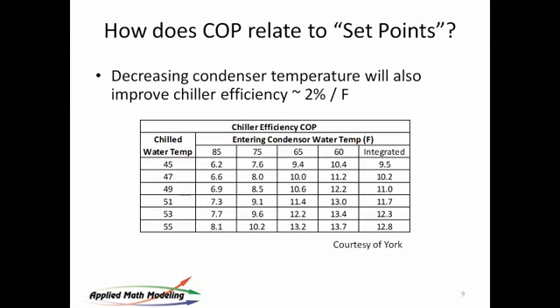The other chart I have here is the condenser temperature itself. If we move along this axis right here, we drive down condenser water temperature, which means the water entering the chiller is colder, therefore that top line in my diagram is moving down, the COP goes up as well. Now you'll notice the COP here, these can get quite high. You see what was 13.7 here, but look at the delta T. My chilled water temperature is 55 degrees, and my entering water temperature 60. I'm only moving this thing 5 degrees. So if you're moving it only 5 degrees, then your COP is quite good. And again, you come up with a similar ratio. As you decrease the condenser temperature, you'll improve the chiller efficiency by about 2% as well.